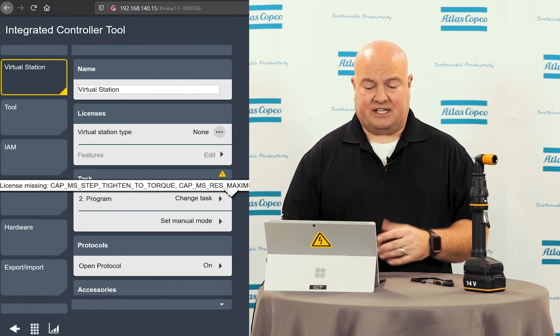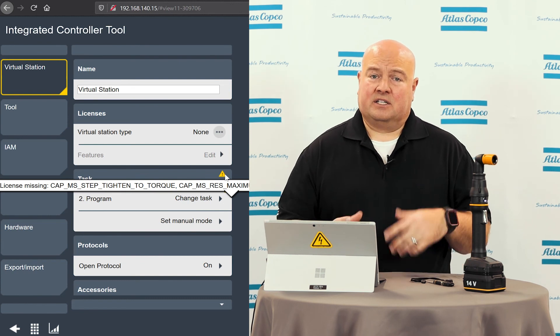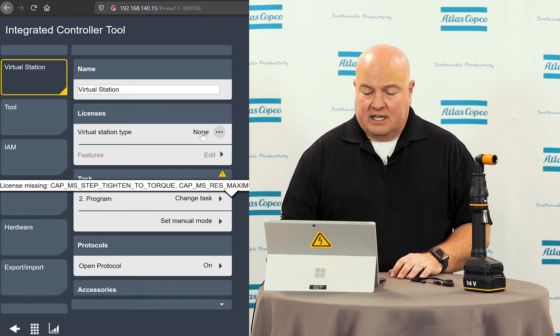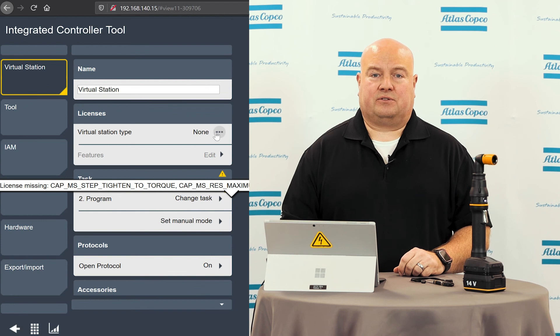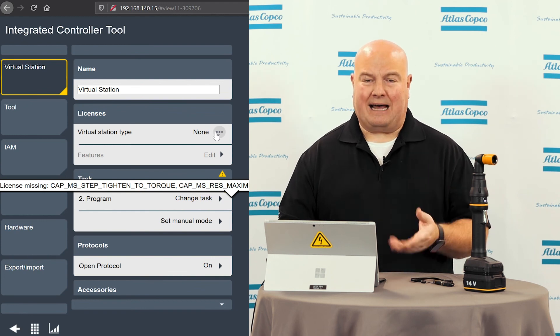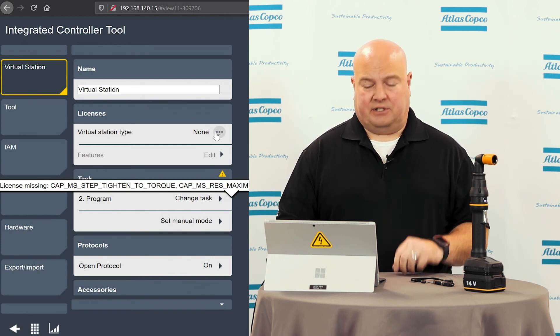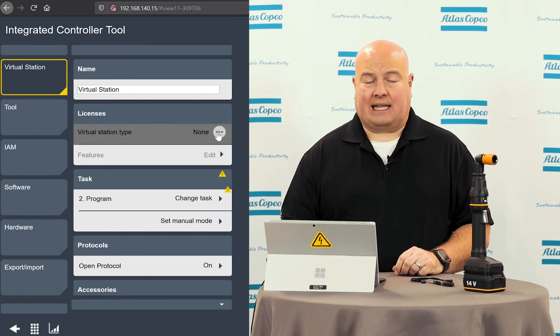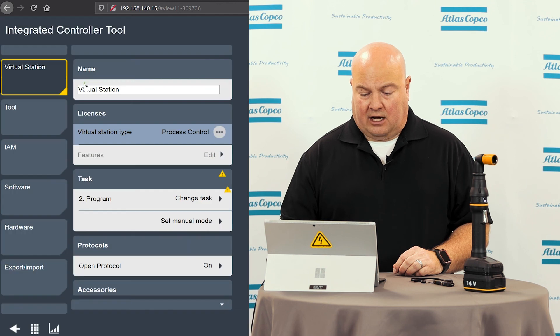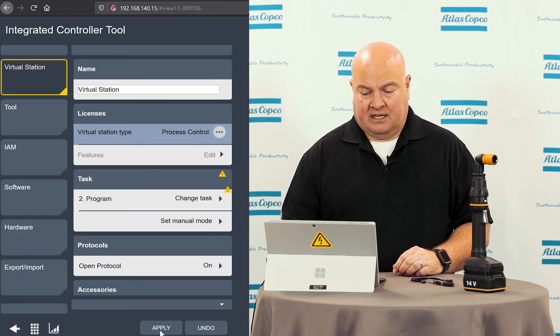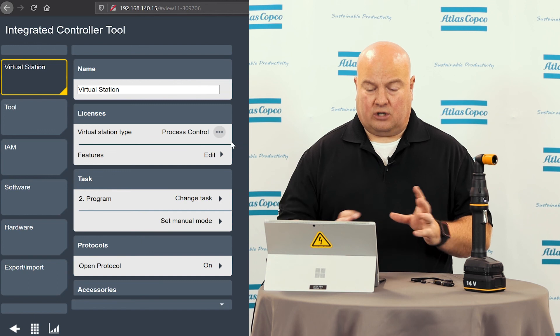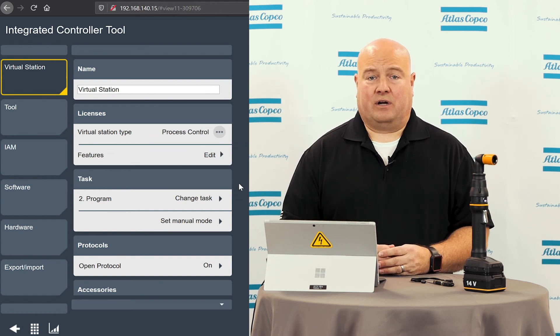This virtual station type as you can see here says none, so it doesn't know what functionality we have. So even though we only have the one process virtual station type on there, we still need to map that to the virtual station just like we do on the Power Focus 6000. So I'll go in here and select that one process control license that I moved over with the portable and I'll click the apply button here at the bottom. As we can see my alerts go away there and now I'm ready to run the tool.